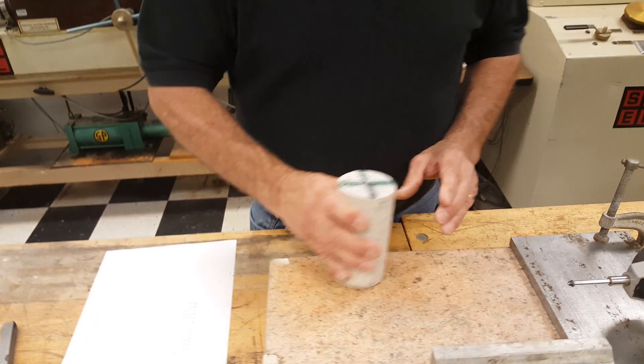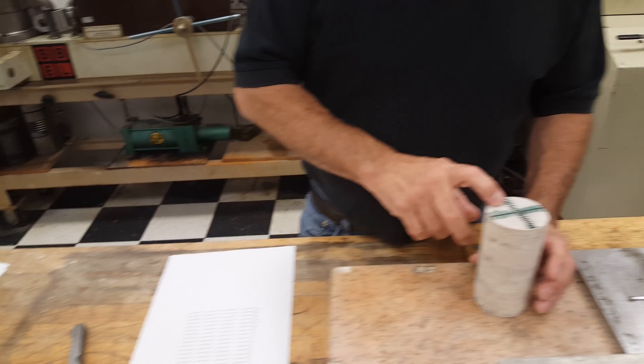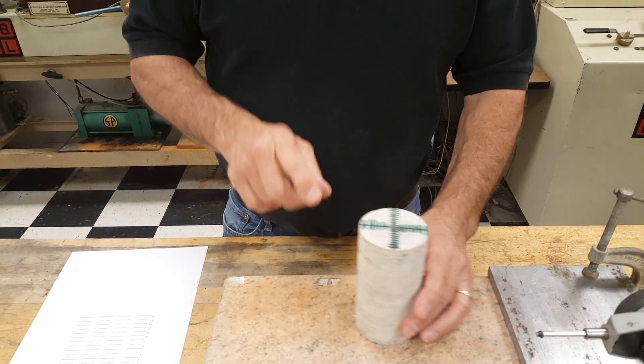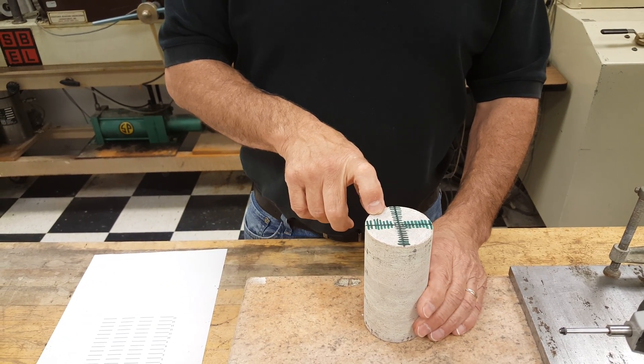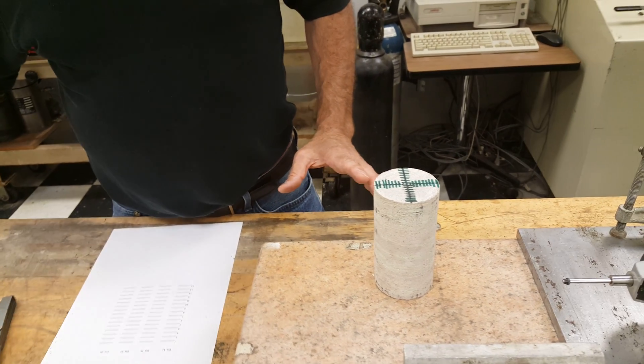The next item is to run a flatness determination of both sides of the core. We've already taken this core and marked it off in one-eighth inch increments. We normally use a system to determine the center of the core, which we've shown here to make it a little bit easier.